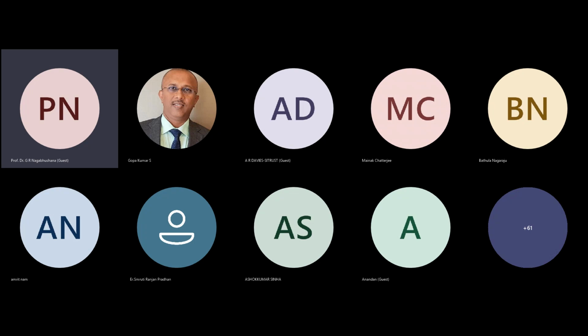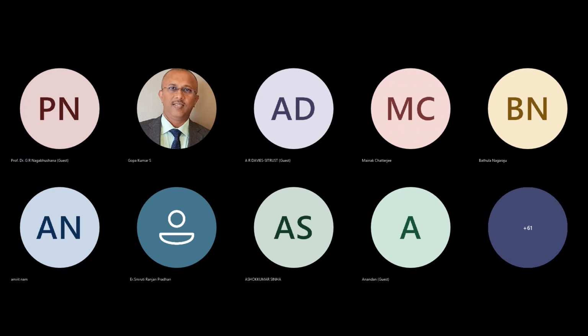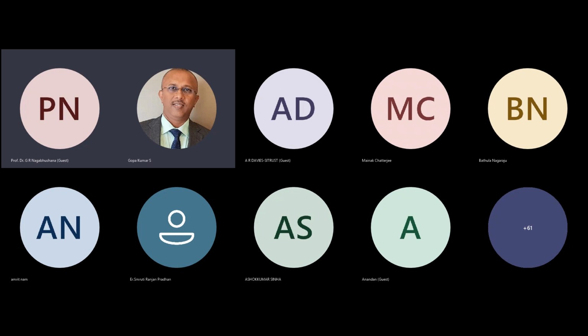But if they tend to be significant, then it needs to be considered. Then the striking distance has to be calculated using that equation, 10 I to the power of 0.6. If you use I as 2 kiloamperes, you will get a slightly different number. 2 to the power of 0.6 is approximately 1.5, so it comes to about 15 meters. That's the radius of the rolling sphere: 15 meters instead of 20 meters. That's why the standards use 20 meters, which may cover closer to about 2-3 kiloamperes also. That's it. Yes, thank you. Thank you very much, sir.